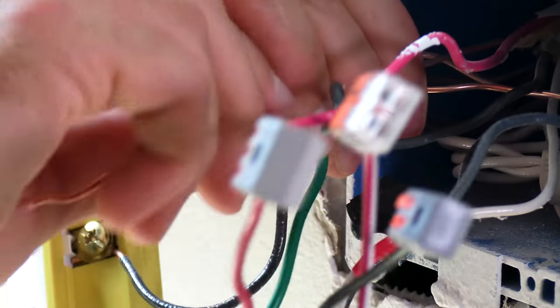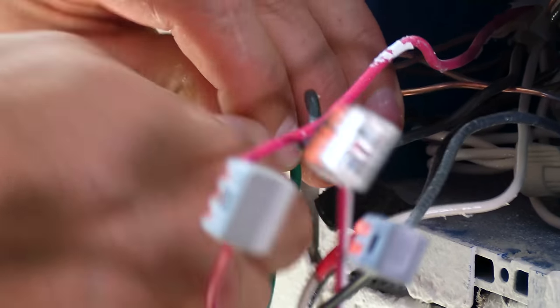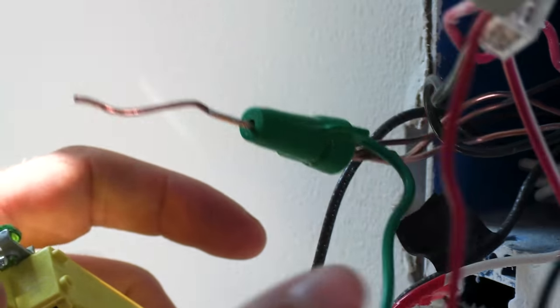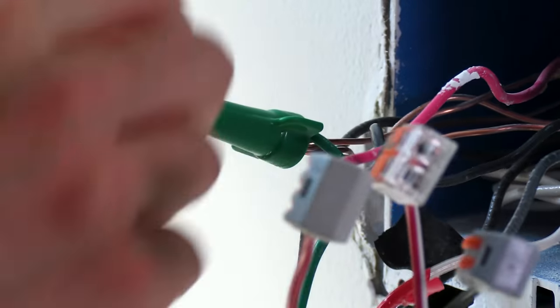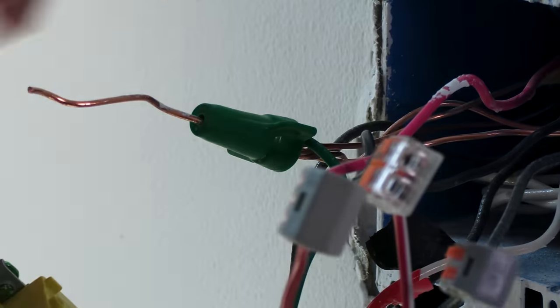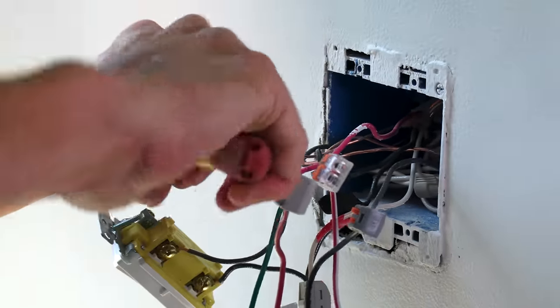So, now this is my mechanical connection that's required by code to incorporate all my grounds. Yep, tug test reveals that it's firmly attached. So, now my dimmer's grounded. My grounding continuity is complete. And all I need to do is wrap this around my single pole switch.